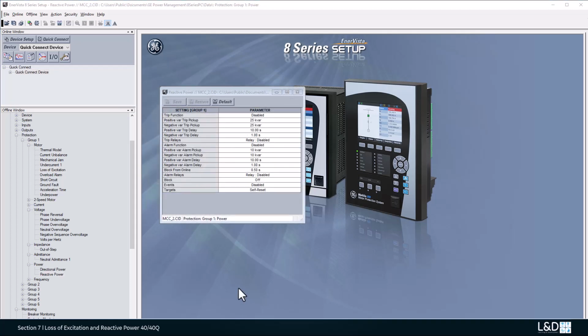In a synchronous motor application, the reactive power element can be used to detect the excitation system malfunction, for example, under excitation, loss of excitation, etc. Once the three-phase total reactive power exceeds the positive or negative level for the specified delay, a trip or alarm occurs indicating a positive or negative kVAR condition. VT fuse fail detection can be used to block this function.